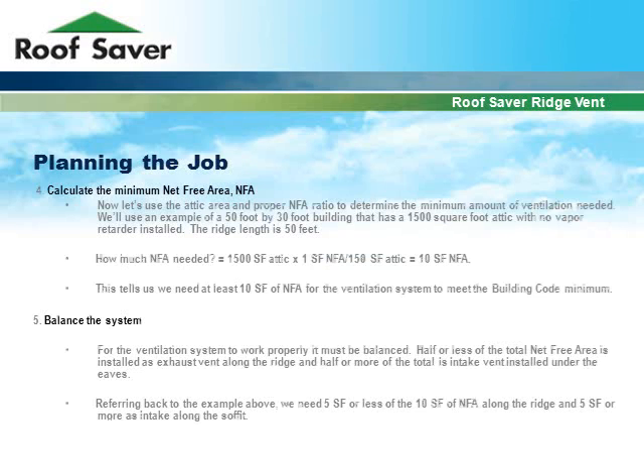Now let's use the attic area and proper NFA ratio to determine the minimum amount of ventilation needed. We'll use an example of a 50 foot by 30 foot building that has a 1,500 square foot attic with no vapor retarder installed. The ridge length is 50 feet. To find the required net free area, multiply 1,500 square feet by the 1 to 150 ratio. This tells us we need at least 10 square feet of net free area for the ventilation system to meet the building code minimum.